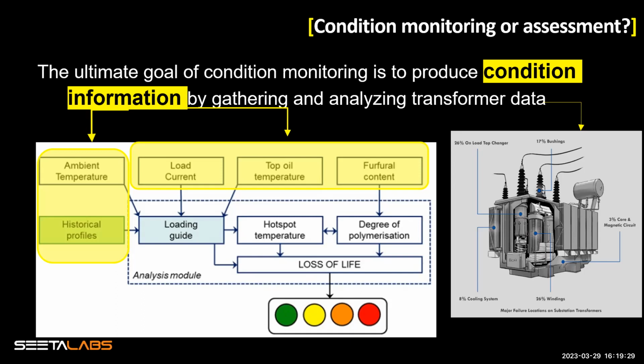Take, for example, the picture on the left side of your screen. You have some parameters: ambient temperature is a parameter, load current and the loading pattern of the transformer is a parameter, and top oil temperature is a parameter, which you can measure.